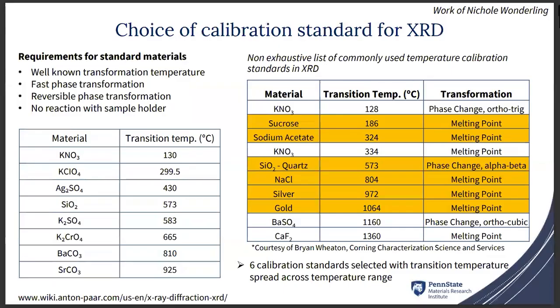For that, we can use a standard material that has a well-known transformation temperature, a fast phase transformation. This transformation needs to be reversible, and it should have no reaction with the sample holder. What was used by Nicole for this study is 6 different materials that have a sharp melting point or phase change across the different temperature range this accessory can achieve.